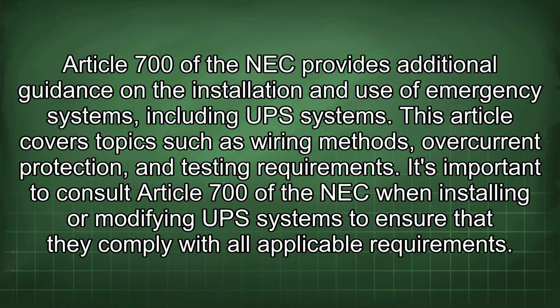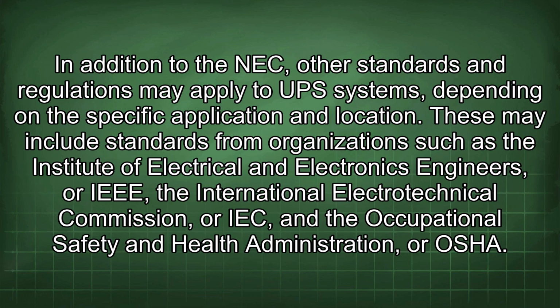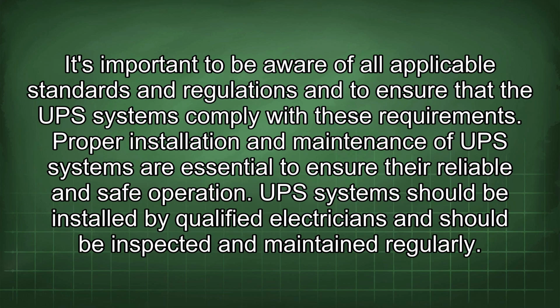It's important to consult Article 700 of the NEC when installing or modifying UPS systems to ensure that they comply with all applicable requirements. In addition to the NEC, other standards and regulations may apply to UPS systems depending on the specific application and location. These may include standards from organizations such as the Institute of Electrical and Electronics Engineers, or IEEE, the International Electrotechnical Commission, or IEC, and the Occupational Safety and Health Administration, or OSHA. It's important to be aware of all applicable standards and regulations and to ensure that the UPS systems comply with these requirements. Proper installation and maintenance of UPS systems are essential to ensure their reliable and safe operation.